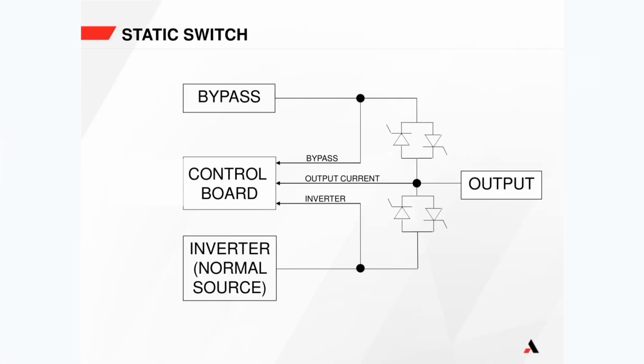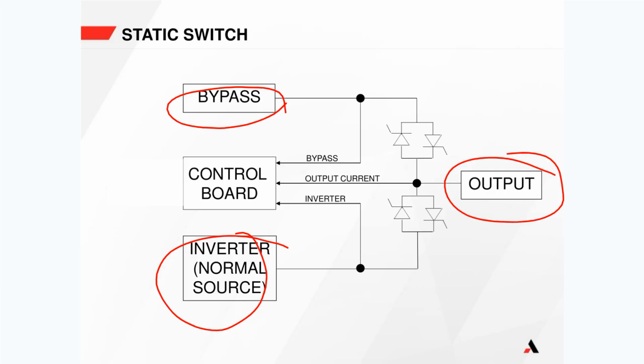And obviously, in a UPS, we have our inverter source, we have our bypass source, and we have our output. So in normal circumstances, we have the inverter static switch on. So power will flow from the inverter out through this static switch to our output circuits here. This static switch will be off. We will have bypass power here ready to go if necessary, but this static switch is off, so it is not conducting and will not allow the bypass to pass through to the output.